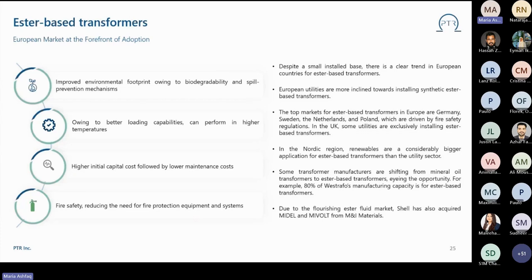Similarly, if we talk about the fire safety aspect of ester-based transformers, the flash point and fire point of ester is very high compared to mineral oil. As a result, it significantly reduces the requirement of safety equipment where the transformer is installed, and it is extremely suitable for indoor environments.